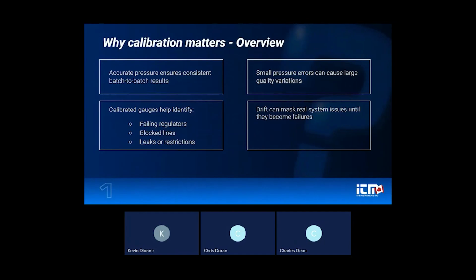So, in any pressure-based system, accurate pressure ensures consistency. Even small pressure errors can lead to large variations in performance output. The system may be operating, but it's no longer operating as intended. Calibrated gauges provide visibility into what's actually happening inside of a system. They help identify issues like failing regulators, blocked lines, leaks, or restrictions before they turn into massive issues. When a gauge drifts out of calibration, it masks those issues. So everything appears to be normal on display while your system slowly moves out of control. And by the time this becomes obvious to the technician working, it's usually already caused downtime and safety concerns. We'll dig into some industry examples shortly. But overall, that's why calibration isn't just a requirement. It's how you protect your process from silent drift.